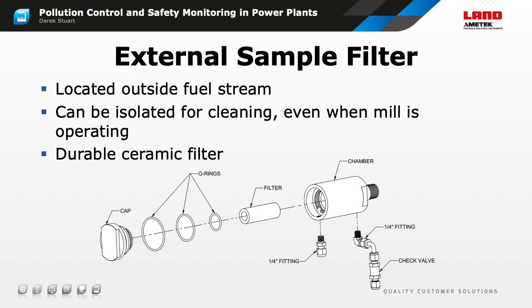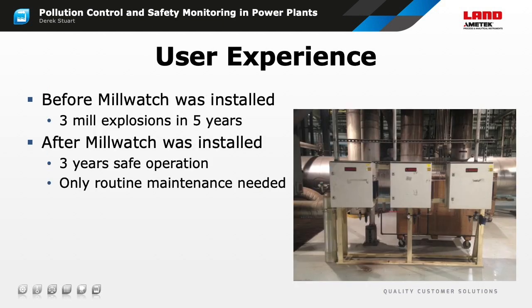This device consists of a sintered ceramic filter mounted in a stainless steel body. By placing the sample device outside the stream of pulverized fuel, we can isolate it and remove the filter for cleaning even when the mill is in operation. So far, we've discussed the concepts behind the detection of spontaneous heating and spontaneous combustion for plant detection. Now let's look at some concrete examples where operators are using these analyzers to enhance the safety of their operations.